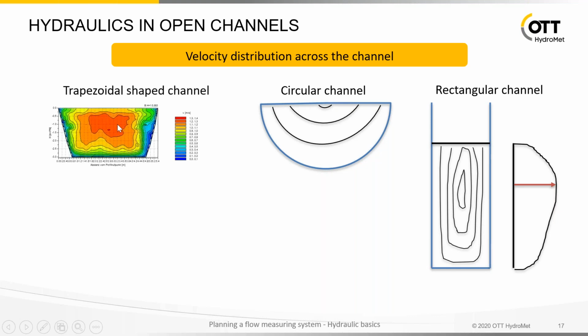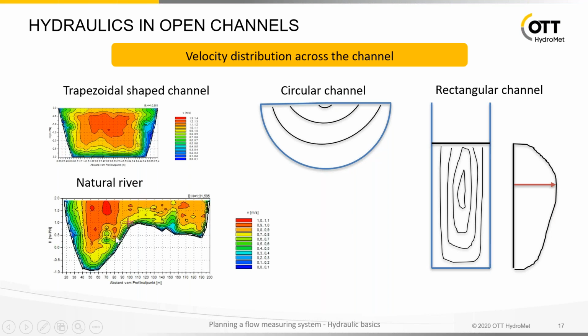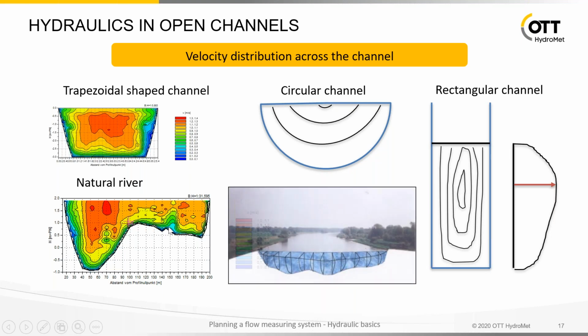If you look at trapezoidal shaped channels, also here it's possible, if it is a very narrow and very deep channel, that the maximum velocity will dip in, so will drop below the water surface. If you have natural rivers, it can be that you have two maximum velocity areas depending on the shape of the cross section, the bathymetry. And what is always very important is that the distribution of your velocity across the channel should be homogeneous and predictable. Because finally, with your flow meter, you're measuring somewhere in the cross section, and you need to build up a relationship between your local measured velocities and the average velocity in the channel.